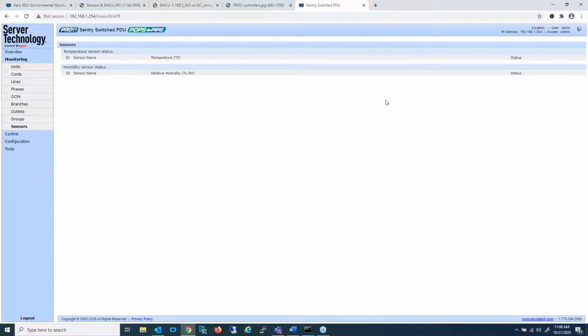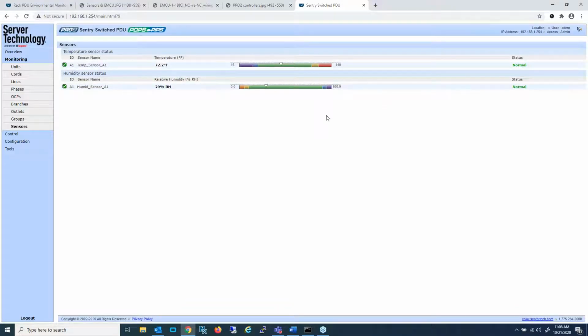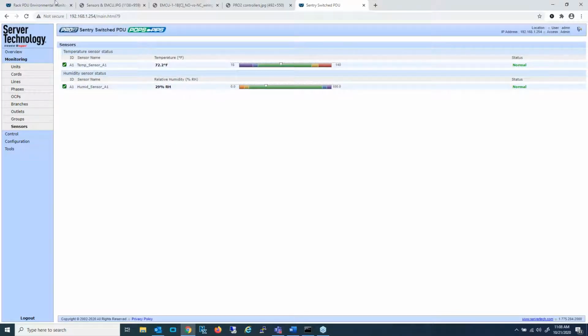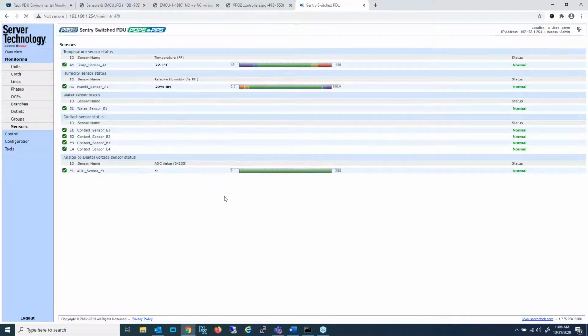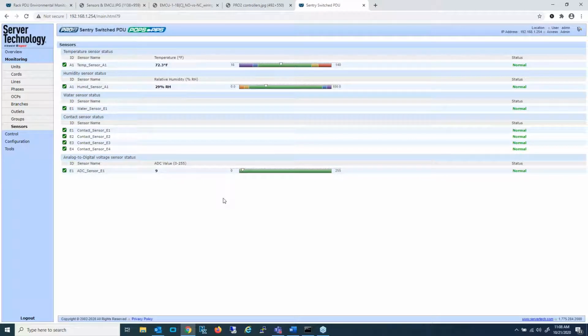So at this point, I am going to attach a temperature humidity sensor to the PDU. And upon refresh, we now find it has discovered both temperature and humidity. So it is really that simple. Just clip the cable in, wait a moment, and you have the readings. I will now attach one of those environmental monitor control units to the system. And since it just refreshed, I will refresh. And again, auto discovery of the device, it really is that simple.